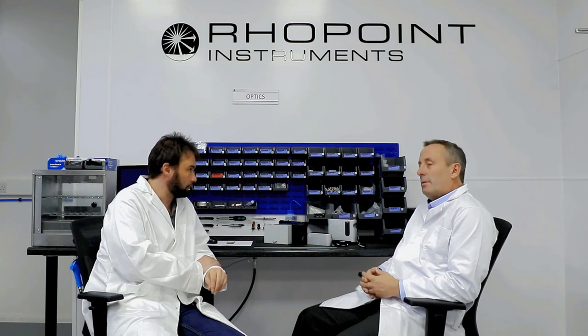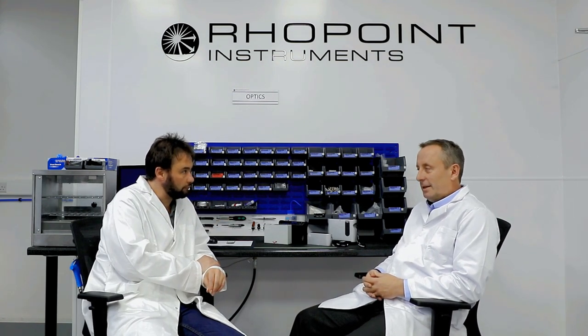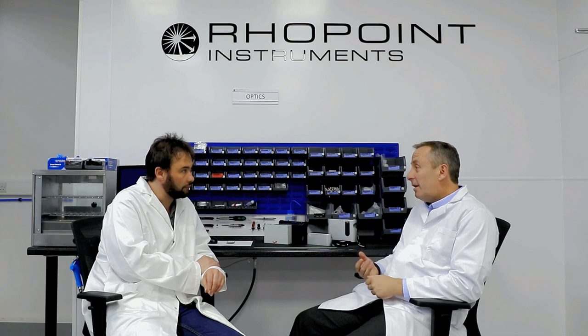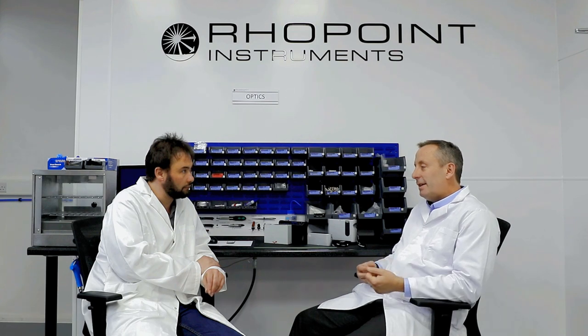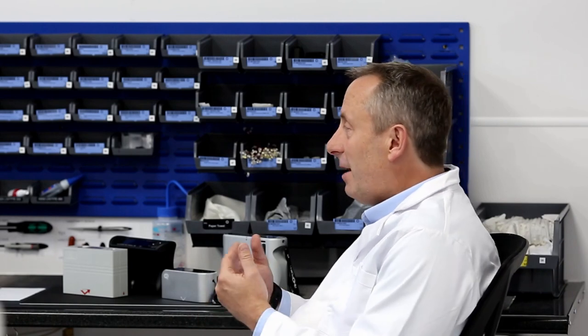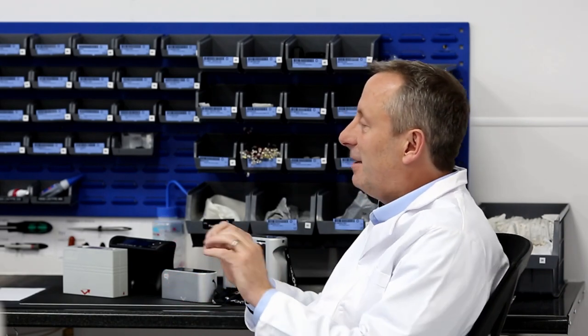And what's it measured in? There's a measurement called the gloss unit, which is related to some international standards. The gloss unit is defined by a relationship to a known physical standard, which is held in some laboratories in Europe and the USA. It's not an SI unit, it's a comparative unit, comparing it to the reflectance of a piece of glass with known properties. All gloss meter manufacturers relate back to these physical standards, so that's how everyone measures the same.